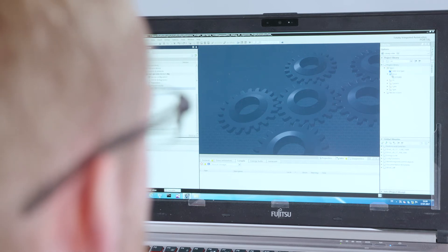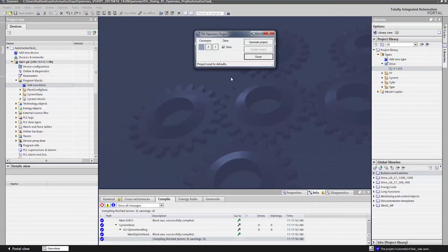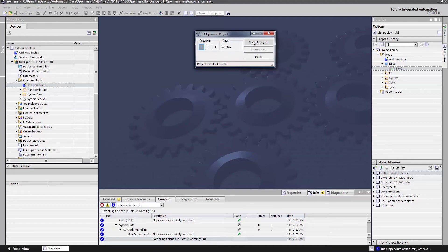Here's a small example. As you can see, the TIA Portal project is empty — the program modules we need to control our machine don't exist yet. Some of the required standardized program modules are in the project library. Now let's automatically generate them with our project generator. I open our program generator, in which we can select the number of conveyor belts we want. Then we click Generate, and the program code for the conveyor belts is generated from our standard module — directly from the library.